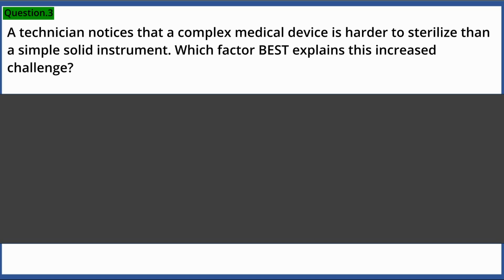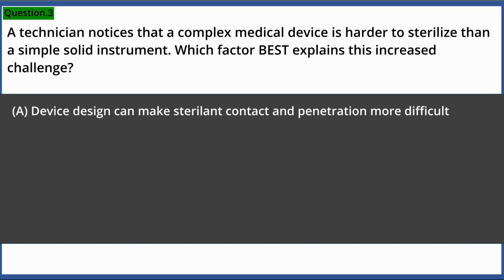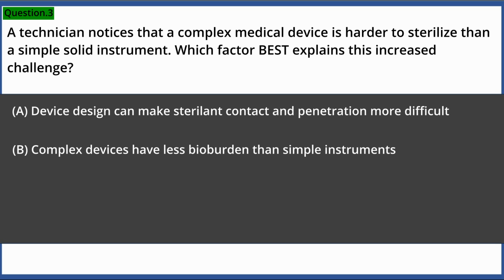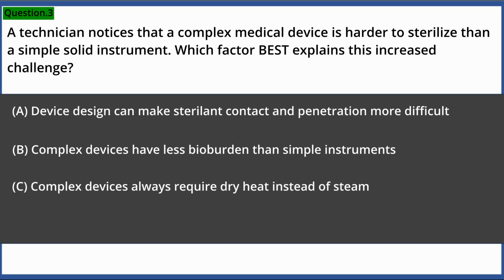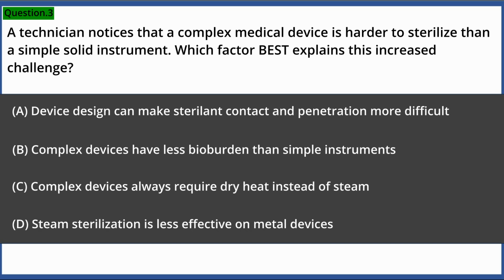A technician notices that a complex medical device is harder to sterilize than a simple solid instrument. Which factor best explains this increased challenge? A. Device design can make sterilant contact and penetration more difficult. B. Complex devices have less bioburden than simple instruments. C. Complex devices always require dry heat instead of steam. D. Steam sterilization is less effective on metal devices. Answer. A. Device design can make sterilant contact and penetration more difficult.